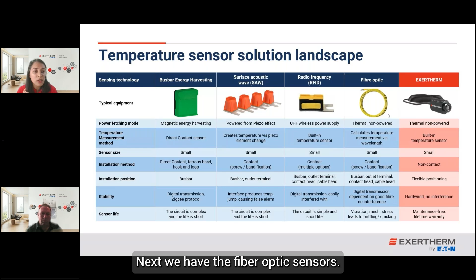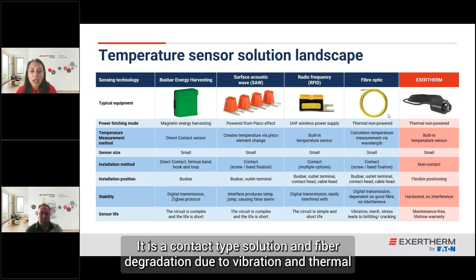Next, we have the fiber optic sensors. They are thermal, non-powered sensors, and they calculate temperature via a wavelength. It is a contact type solution, and fiber degradation due to vibration and thermal stress over time can cause the fiber to become brittle and crack.